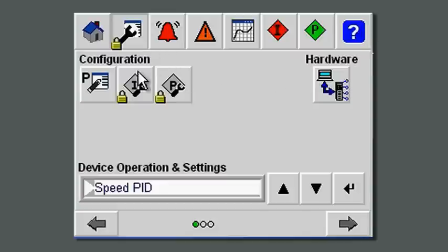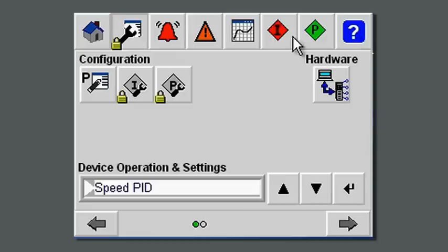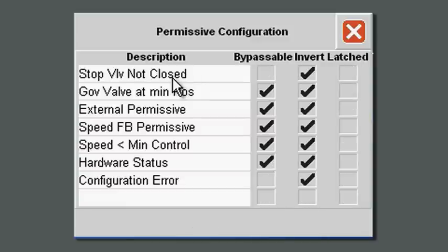From the interlock page, you can see configurable interlocks that you can set up to make the operation of your turbine safer and fit your particular process. If you don't have these particular interlocks or trips, you don't configure them and they won't interfere with your operation. When you come into the permissives, they are there to place certain inhibits or allow the turbine to be started if certain alarms are not present. You configure the permissives from this screen, and again, if you don't use them or don't have them in your installation, you don't configure them and they don't interfere with anything.